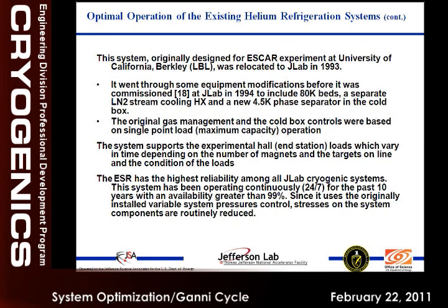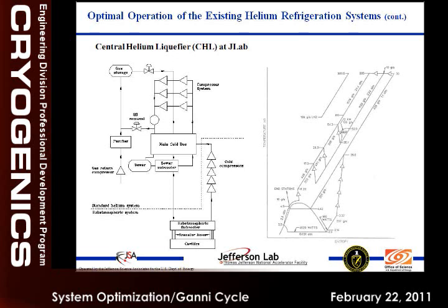But now we use it as a floating pressure plant, where we do not allow this plant to operate at 18 atmosphere all the time unless I ask for it. So that made this plant very reliable. Now it operates at almost 99% availability, except last year we had more turbine failures than ever.